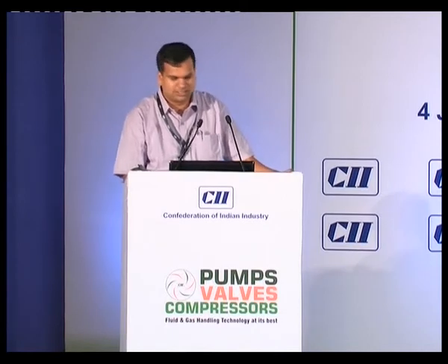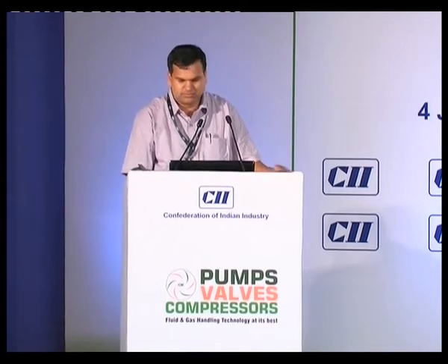So what we can do is split the total requirement, rather than going with a single pump, into small 2 or 3 pumps or maybe 4 pumps. Whenever the requirement is small and can be catered by a small pump, that individual pump can be on and the requirement will be met with lesser energy. Moreover, we can go with a variable speed drive, which will adjust the speed of the pump and exactly support the requirement.